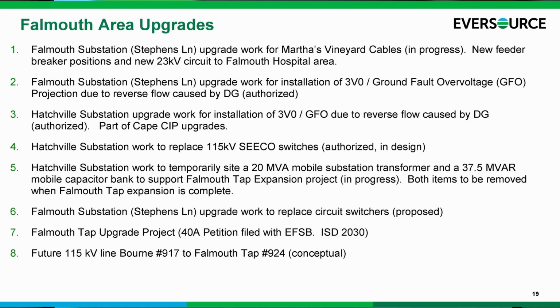Items 2 and 3, about ground fault overvoltage prevention, are driven by protection standards due to DER interconnection. So 2 and 3 are driven by system protection and safety reasons. We need to upgrade existing protection at these stations to prevent DERs, distributed energy resources like solar, from feeding a fault into the transmission system. That could be a safety concern as well.